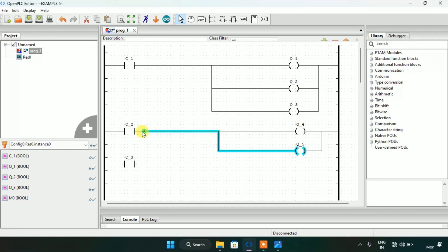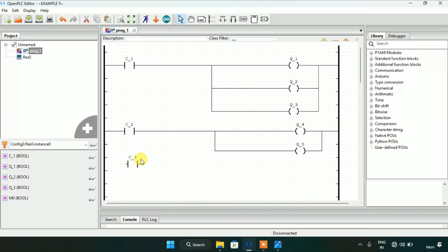When I modify the c2 normally open contact to true, coils q4 and q5 will go true. So I will attach q4 and q5 in parallel and join these pins with the c2 contact. The last condition is when I modify c3 to true, coils q2 and q5 will go false. That means I have to add c3 as a normally closed contact in series with coil q2, and the same goes with q5.